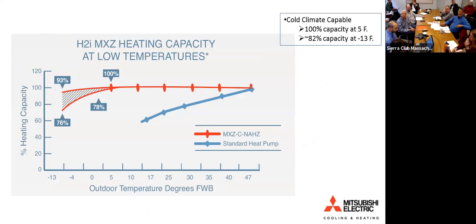Here's the question that you asked. So, this is a chart of the way that these systems work. Outdoor temperature, heating capacity. At 47, 45 degrees, old heat pump technologies, which gives the whole industry a bad name, we're still calling it a heat pump, started to derate at 47 degrees, and by the time you got to 17 degrees outdoor temperature, it was blowing cold air. And the advent of what we call hyperheat that came along, now only about 7 or 8 years ago, completely changed the industry. We've got 100% capacity to 5 degrees Fahrenheit, which we don't see very often around here. And below that, to minus 13, most of our systems are still operating between 93 and 76% of capacity.